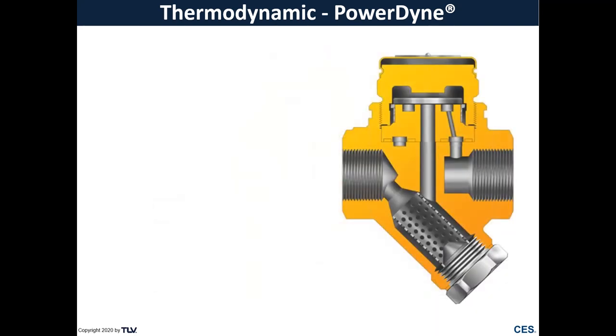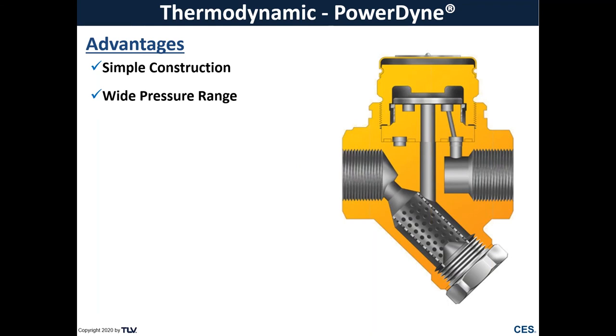Some advantages for the steam trap: this is a very simple construction. Each model has a capability of operating under a wide pressure range. It's a very compact design, and this trap can be installed in any orientation. Being installed horizontally will give a longer life to this trap. Because this trap is made of solid pieces, it can handle very high pressures as well. Certain models can.